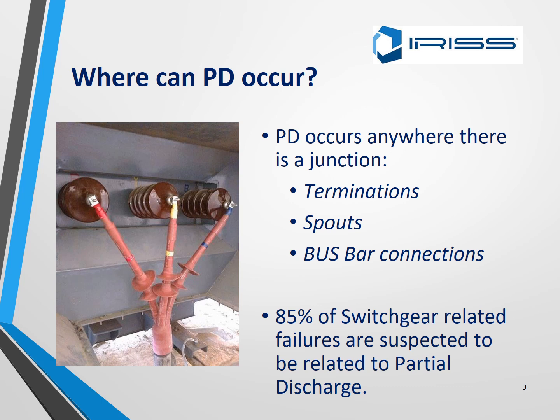Where can PD occur? PD occurs anywhere there is a junction or a man-made termination. The termination is always a weak spot — spouts and busbar connections. 85% of switchgear-related failures are suspected to be related to partial discharge.